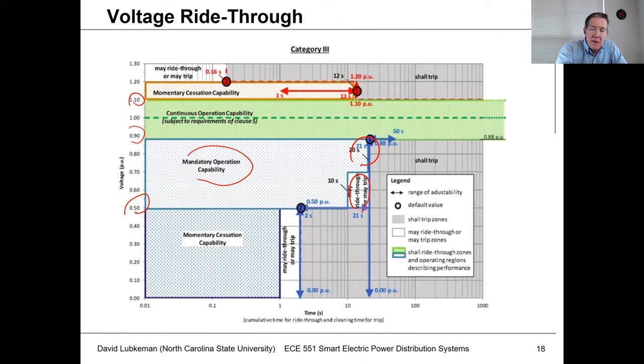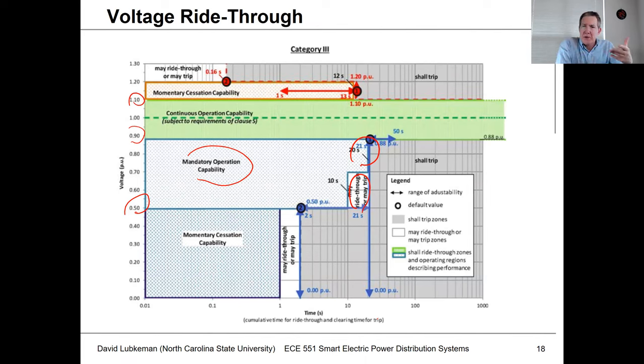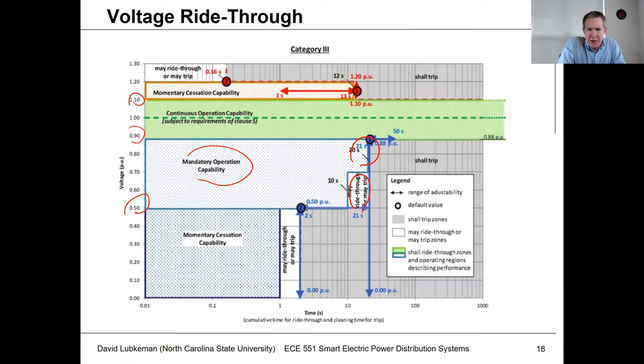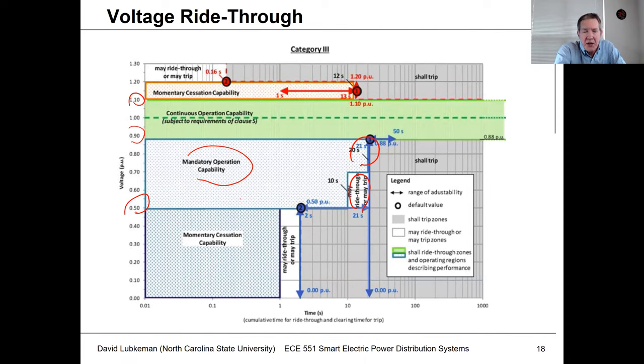Note this time scale is a log scale, not a linear scale. That's a long time for the unit to be hanging in, but keep in mind there are going to be recloser operations and some of these faults take a long time to clear. That's what they came up with in the standards. If you drop below 0.9 and you're above 0.5, once you get beyond that 20-second mark, then you need to trip out.